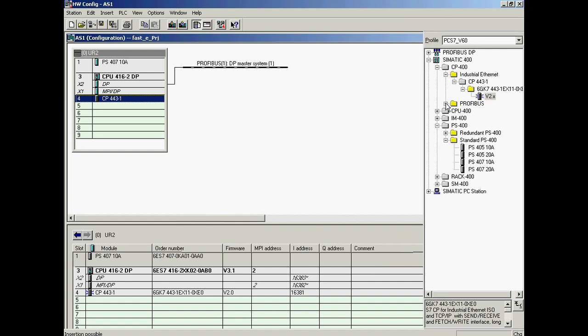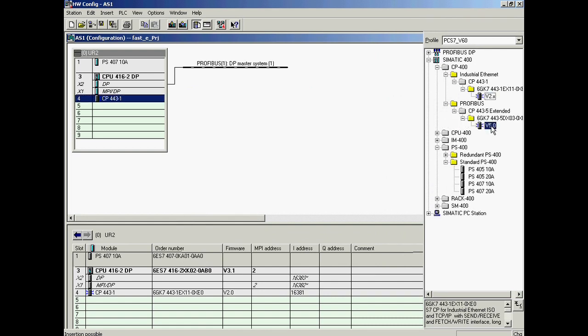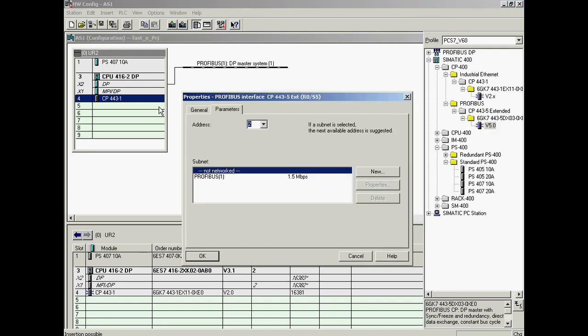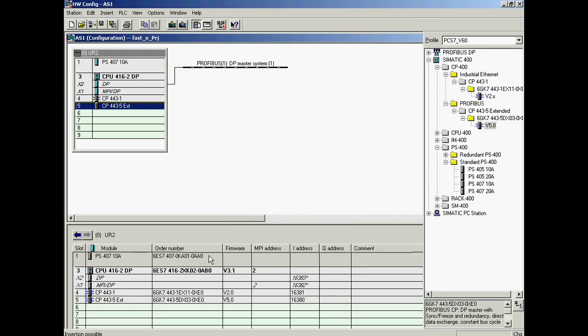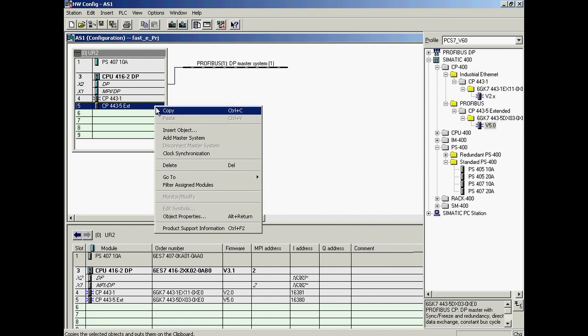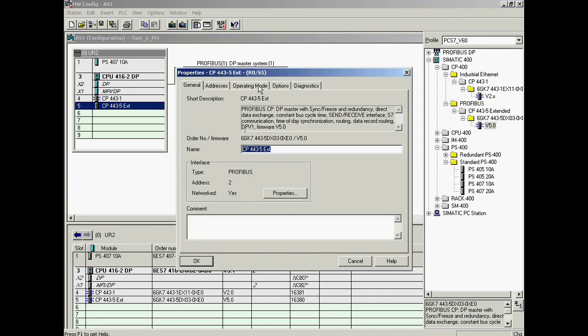The CP443-5 Extended is configured for access to the Profibus. Some adjustments are made in the properties dialog. The first step is to create a new Profibus string which will have the name DP1. The last step is to open the properties dialog and set the CP operating mode to DP Master.